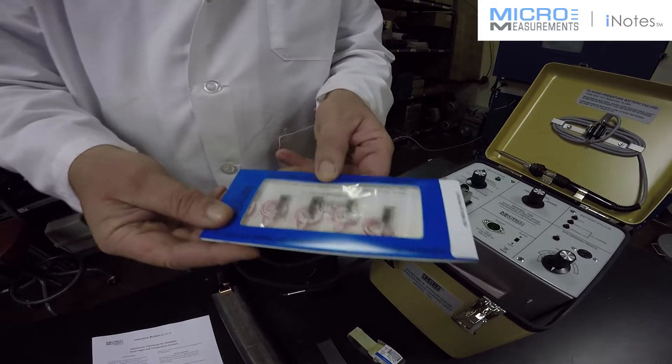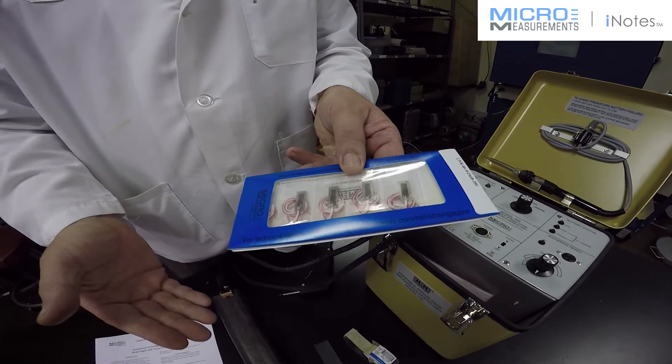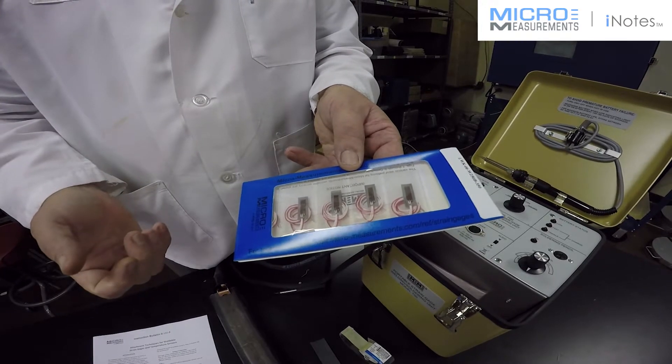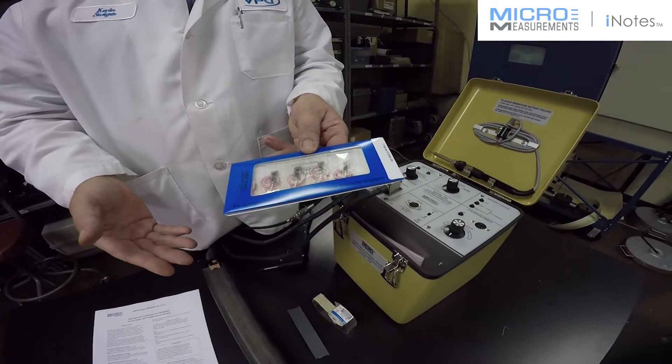The advantages of weldable strain gauges are that you do very minimal surface preparation, which I'll show you here in a minute. You can also install them in adverse conditions, and there are certain types of sealed weldable gauges that can even be installed underwater if necessary.